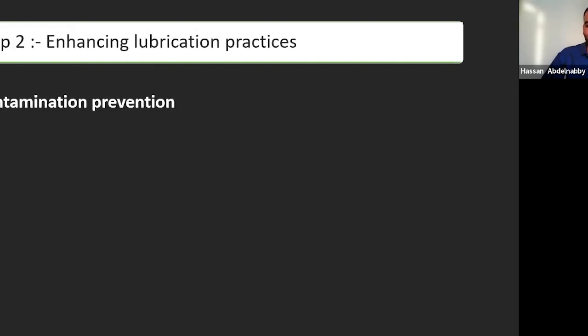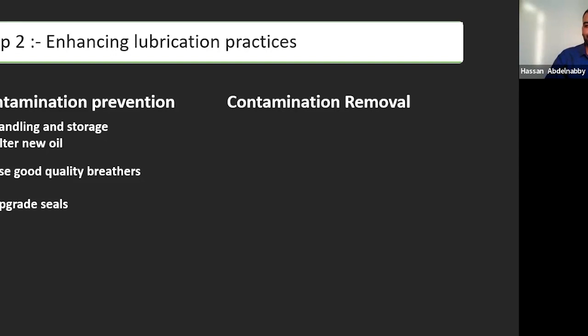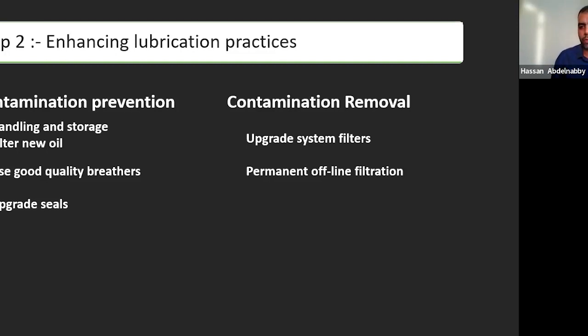Contamination can be prevented or removed. Start with prevention: handling and storage, filtering new oil, using good quality breathers, or upgrading seals to prevent contamination from entering your asset in the first place. But sometimes prevention is not enough and you also need removal — upgrading system filters or considering offline filtration. From my point of view, you need to work on both: prevention and removal.